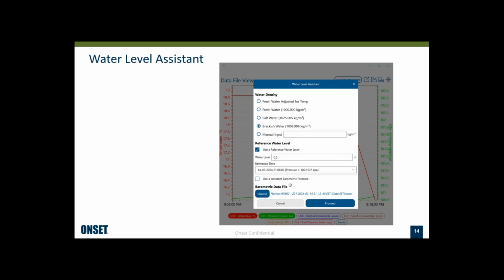For the water level calculations, users who have the MX800 logger, which has the built-in barometric pressure sensor, can get water level directly. So they don't need to use the water level assistant at all. The water level assistant is for users of the MX801 logger, which is the submersible logger. Because of that, it can't measure barometric pressure. So they need another logger, an MX802 logger, deployed in the air or nearby to record barometric pressure, and that gets combined with the water pressure data to calculate water level.